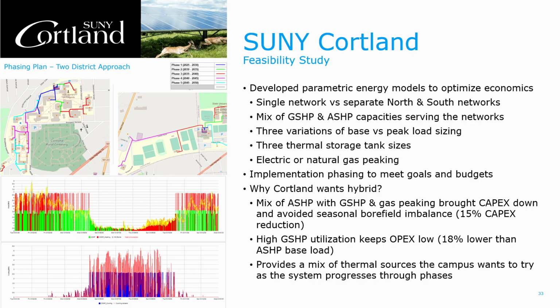So we looked at sizing the heat pumps for a certain percentage of the peak load. So typically 50, 60, or 70% of the peak will cover anywhere from 80 to 95% of the annual load. And then using existing infrastructure boilers or even electric boilers for that remaining peak and last 5 to 10% of the annual. Also looked at different thermal tank storage sizes and, like I said, electric or natural gas peaking equipment.